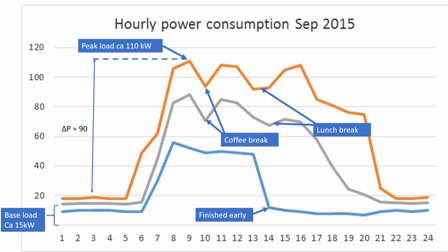What you need to ask yourself here is whether there is something turned on during nights and weekends that doesn't really have to be turned on. A visit to the plant during nighttime may be helpful here to find such things. In the graphs, you can clearly see how production starts from 5 to 6 a.m. as the power load increases dramatically. Here, it is useful to look at what the difference was between the days of minimum load and maximum load and try to understand why there's a difference. We can also clearly see in the graphs when breaks occur during the day. It appears here, though, that all equipment is not turned off when taking breaks.